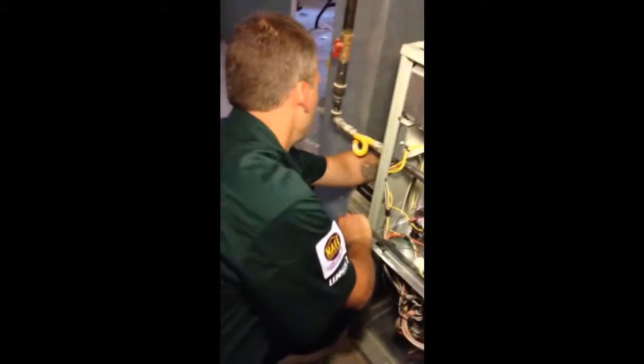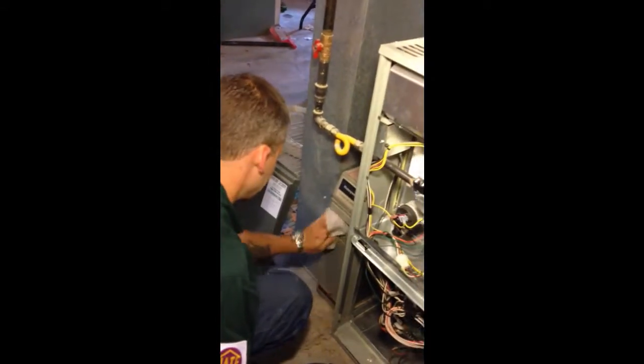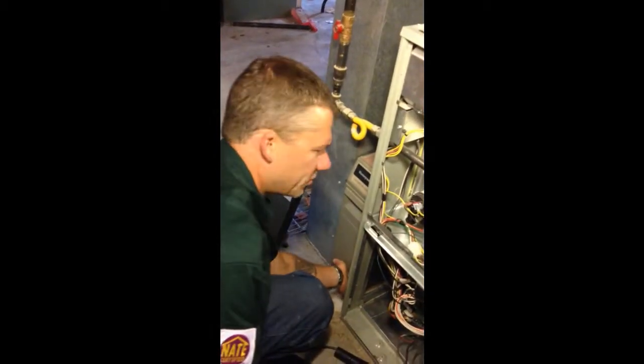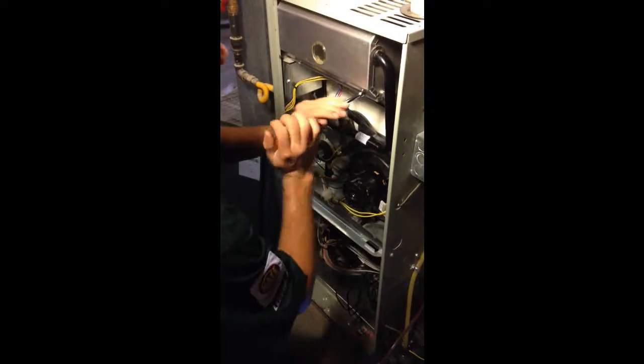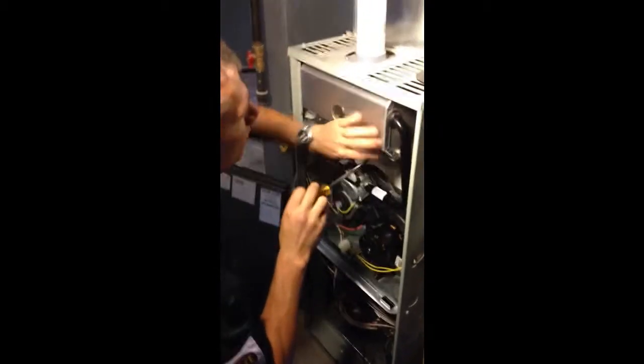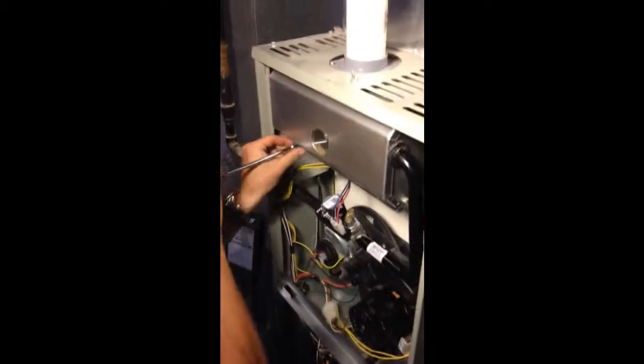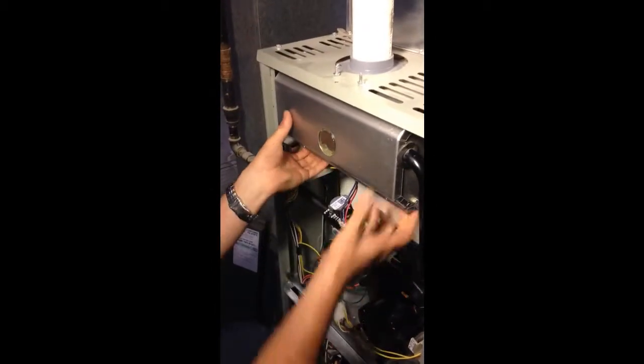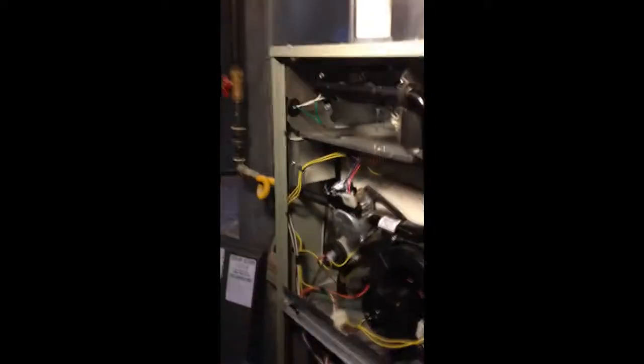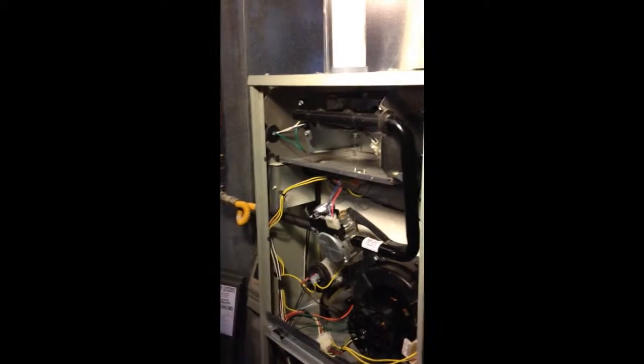So then we wipe off the AC. Everything works better when it's clean. What I'm going to do is pull off the burner box cover. This gives me access to the burner box, the igniter, the flame rod. And right here is the igniter, and you unplug this. Okay, so do you see back there? I don't know how well you can see in there, but it's really, really rusty. Okay. That's not good.